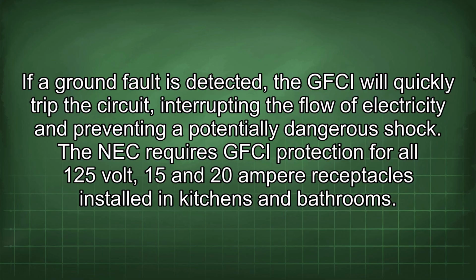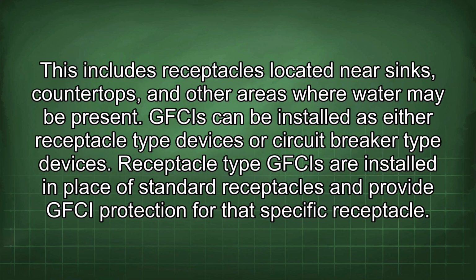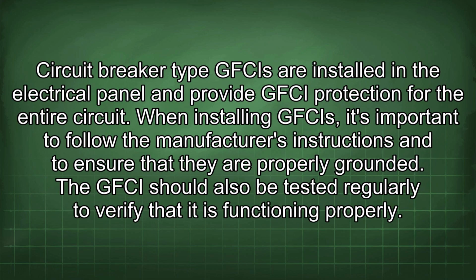The NEC requires GFCI protection for all 125-volt, 15 and 20 ampere receptacles installed in kitchens and bathrooms. This includes receptacles located near sinks, countertops, and other areas where water may be present. GFCIs can be installed as either receptacle-type devices or circuit breaker-type devices. Receptacle-type GFCIs are installed in place of standard receptacles and provide GFCI protection for that specific receptacle. Circuit breaker-type GFCIs are installed in the electrical panel and provide GFCI protection for the entire circuit.